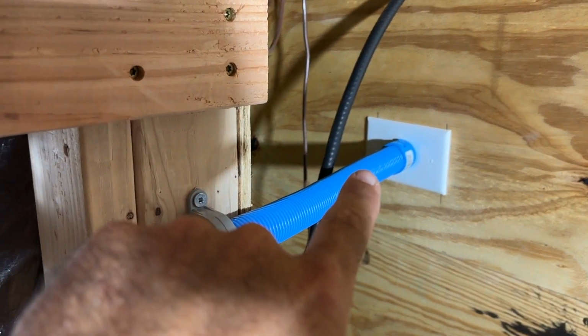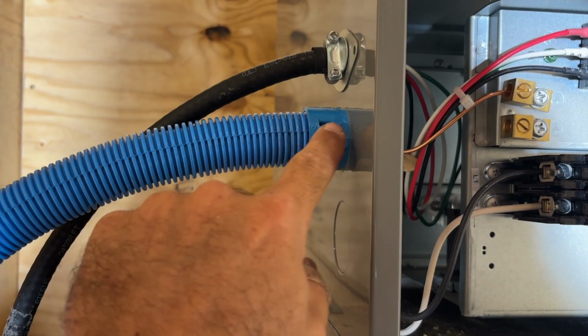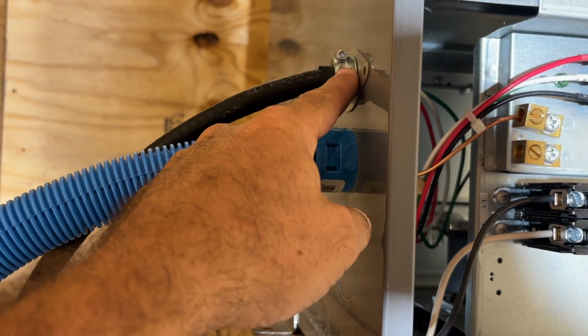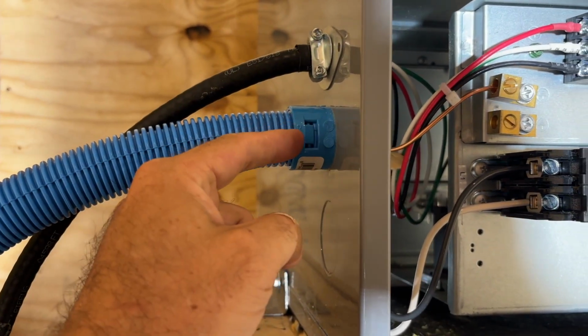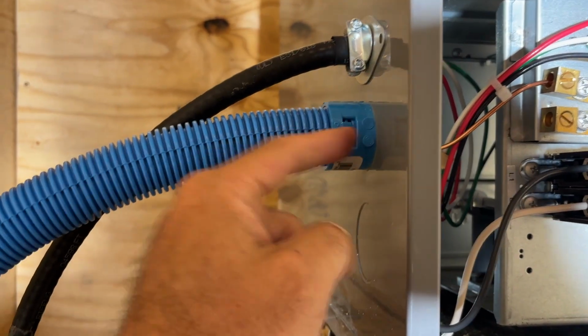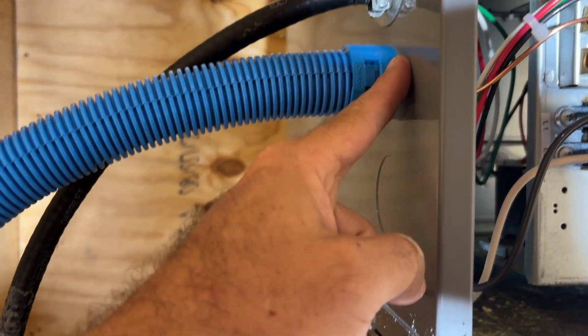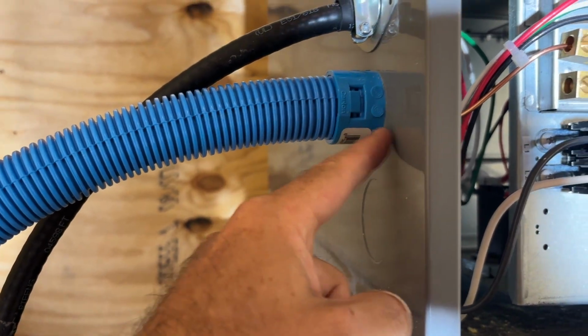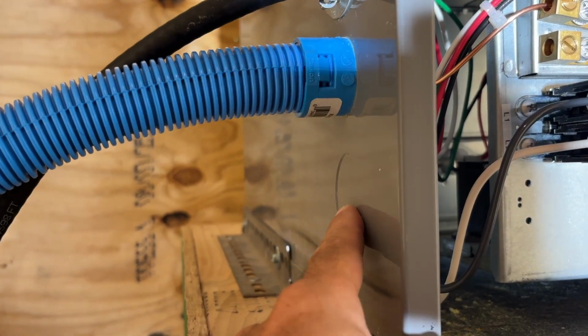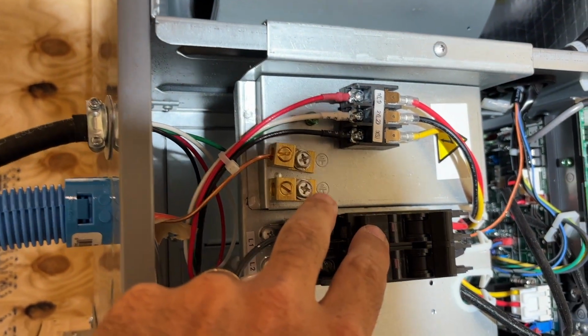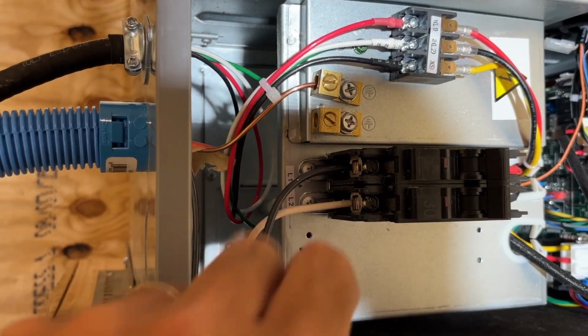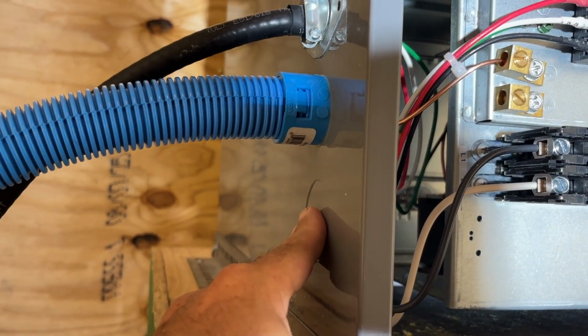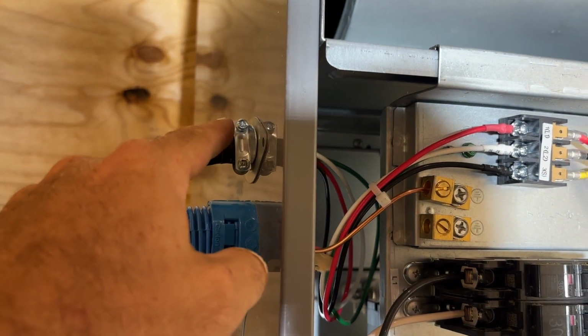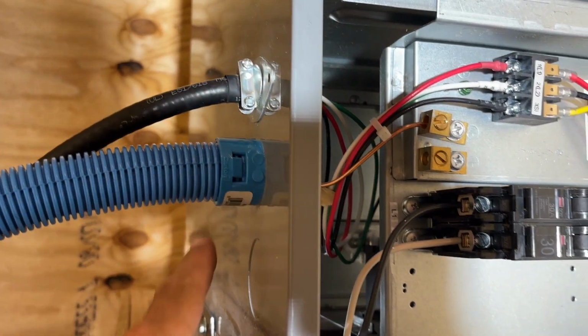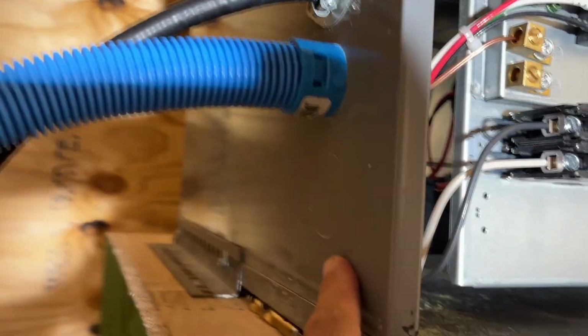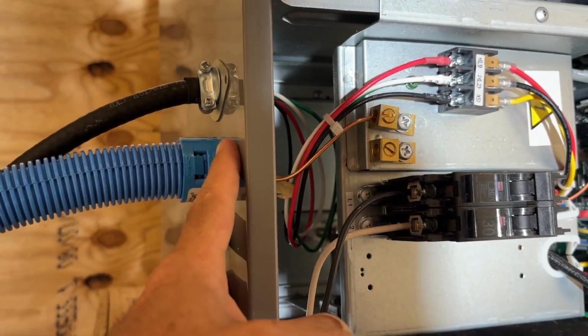So we're running it in some conduit here around. This is a 3/4 inch knockout for 3/4 inch conduit. This is for 1-inch conduit. That's a 1 1/4 inch knockout, I believe, or actually 1 3/8 for 1-inch conduit. And then this one is a little bit bigger. I guess if they had the really big aux heat where you had to run a couple of cables through, or a bigger cable, you could use this bottom knockout. So you got a 3/4 inch, a 1-inch, and this might be like 1 1/4, I think, a knockout there. So you got 3 different options for conduit to run to your unit.